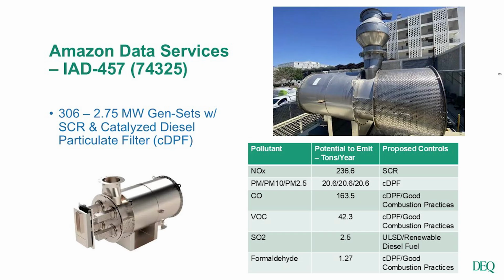The applicant has proposed Tier 4 equivalent controls for the units, including selective catalytic reduction to reduce emissions of NOx, catalyzed diesel particulate filter to reduce emissions of particulates, volatile organic compounds, carbon monoxide, and formaldehyde. And then they're proposing ultra-low sulfur diesel to reduce emissions of sulfur dioxides.